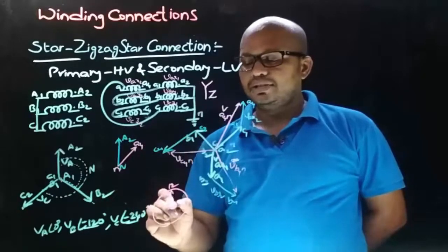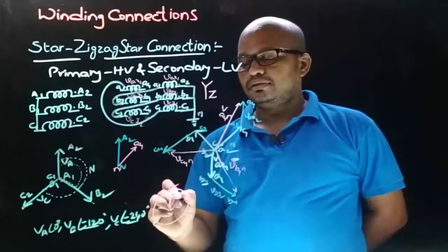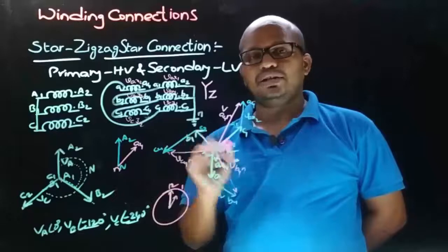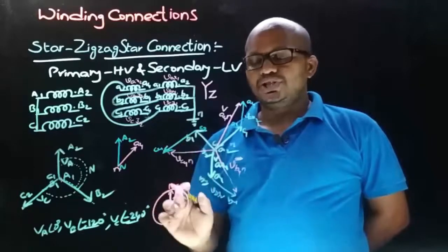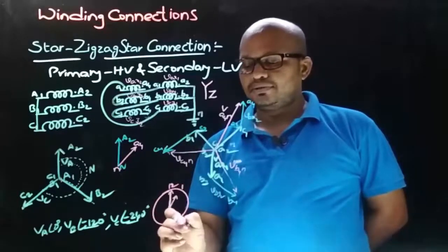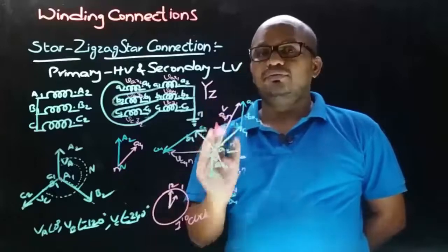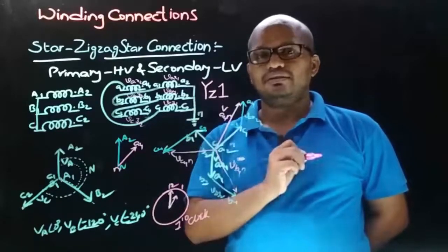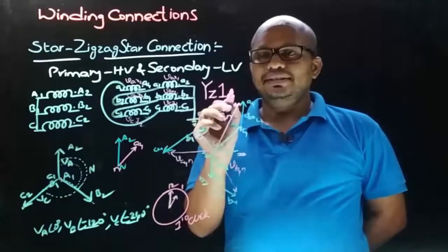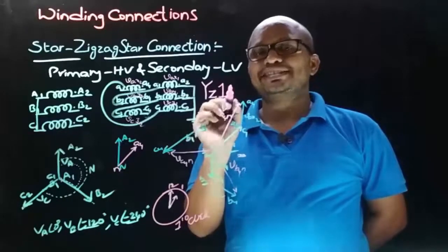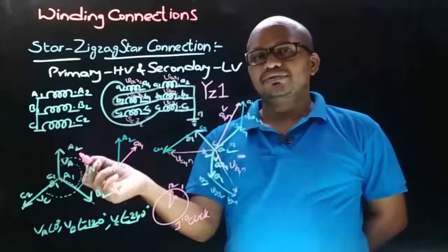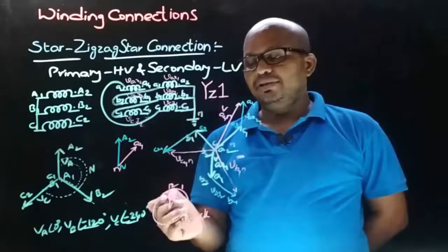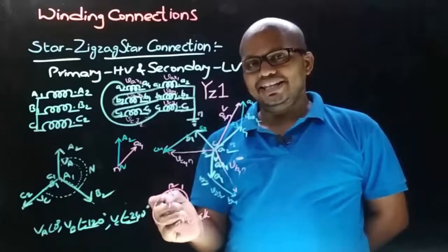Upon placing it, the hour needle is shown pointing towards 1, and these positions in the clock represent 1 o'clock. Therefore, the numeral in the vector group symbol is 1, which indicates the LV side phase unit voltage displacement with respect to the HV side phase unit voltage, and that is given by the angle between the minute needle and the hour needle in the clock.